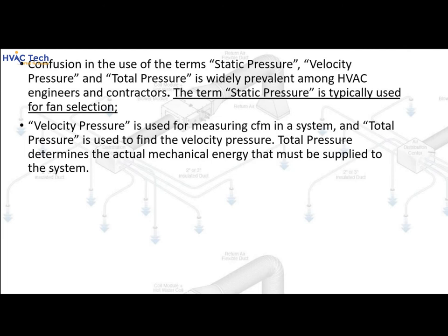Confusion in the use of the terms static pressure, velocity pressure, and total pressure is widely prevalent among HVAC engineers and contractors. Static pressure is typically used for fan selection; velocity pressure is used for measuring CFM in a system; and total pressure is used to find the velocity pressure. Total pressure determines the actual mechanical energy that must be supplied to the system.